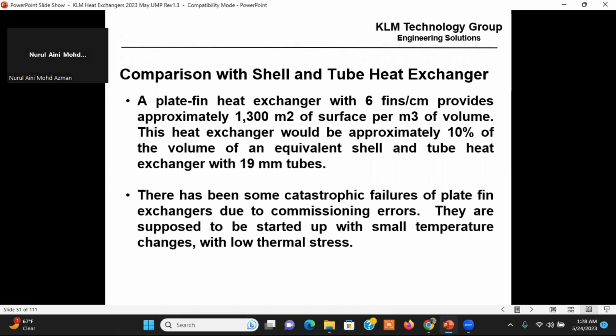been some catastrophic failures of plate fin exchangers due to commissioning errors. They're supposed to be started up with very small temperature changes, very low thermal stresses. It's a soft metal, they're welded together. It's kind of like a paper clip. If I flex it too many times, it's going to break. And if you start them up quickly and you flex the metals, they've actually opened up and let gas come out. And there's been some pretty catastrophic failures of plate exchangers. So you've got to baby them. You've got to start them up with very small temperature changes and very low thermal stresses.